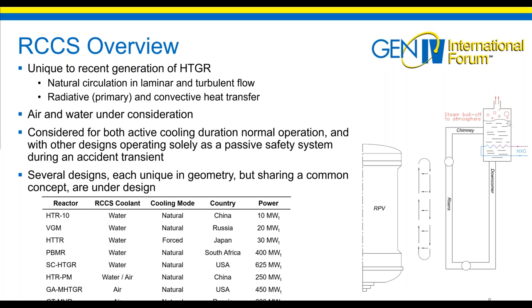There would be a header tank located up high in the plant elevation. The water during normal operations would be driven by a pump, rising through the reactor silo and discharging into this header tank, which would dissipate decay heat to a heat exchange unit that would be the normal way of cooling the reactor silo.